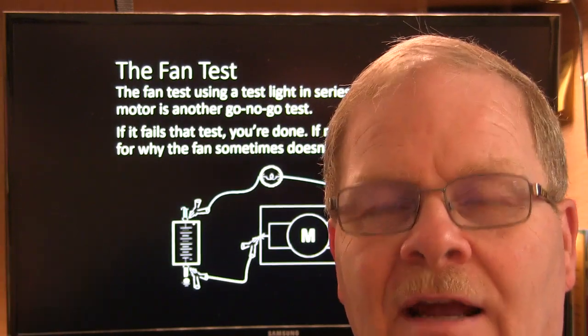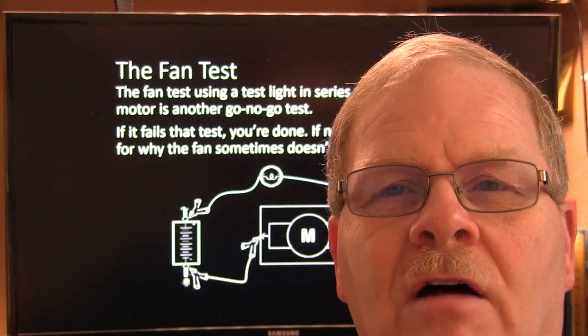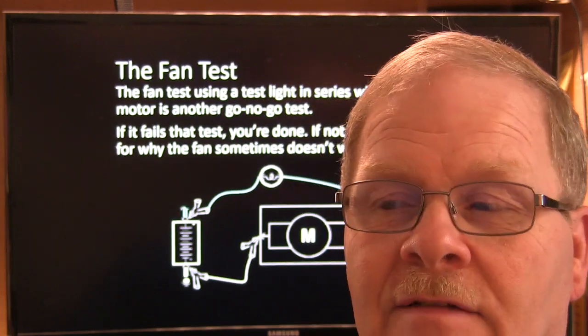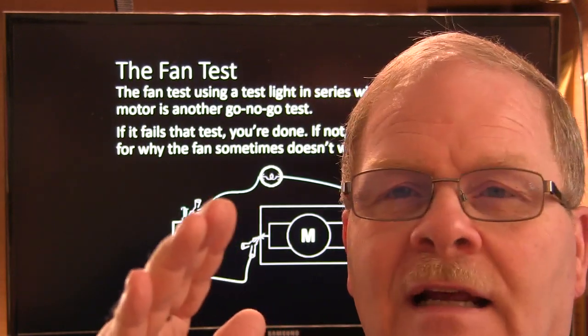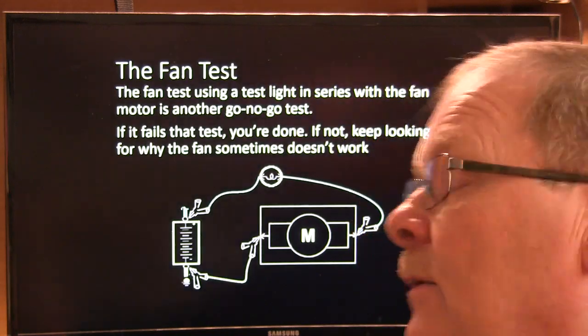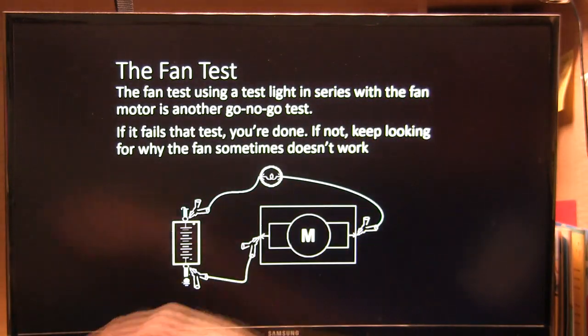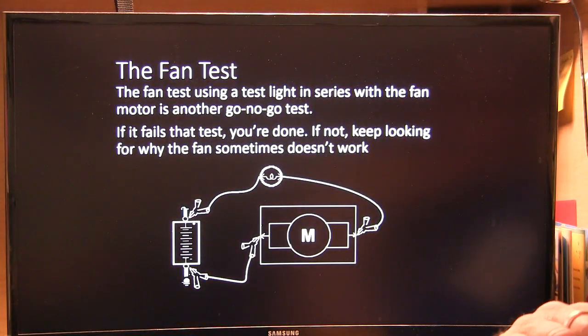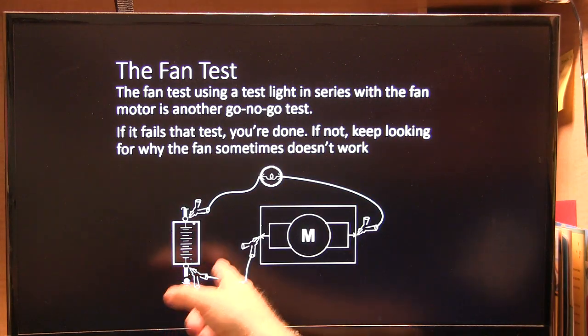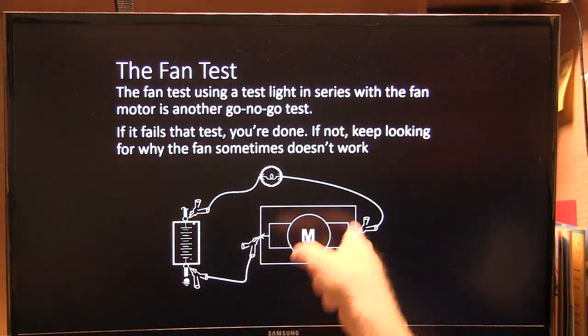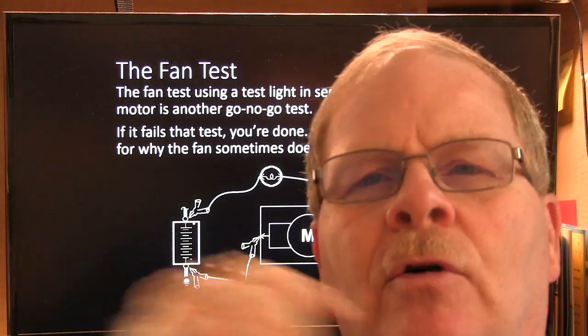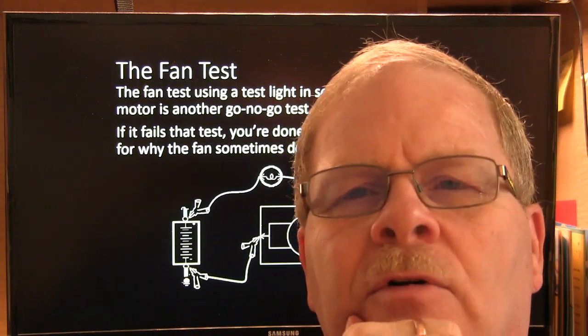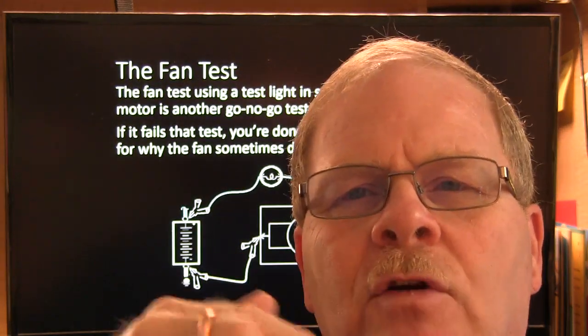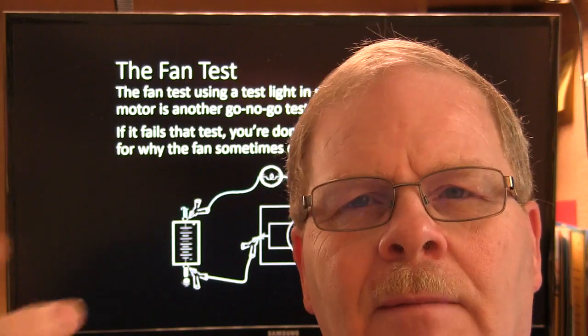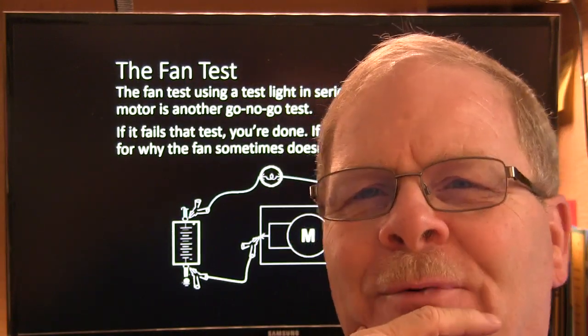That bulb should light up. You turn the fan through. If the light ever goes off, that's a Go-No-Go test, because if that fan ever stops on that dark spot, it ain't going to run even if it gets power. This right here is a little schematic I drew in paint showing how you make that work. You basically hook it up so the light bulb is in series with the fan. You can test a fan motor on the bench, or any other electric motor pretty much the same way, if you can spin it through by hand. Power window motors are hard to do that with.